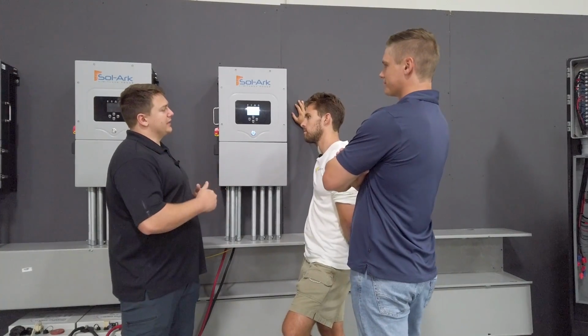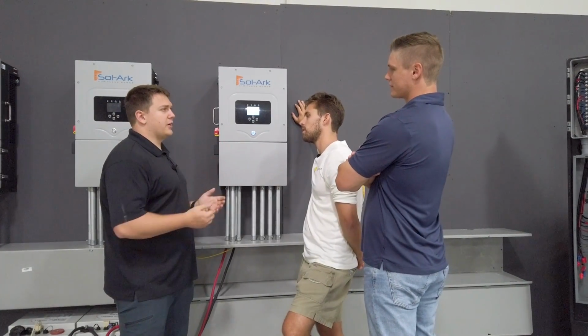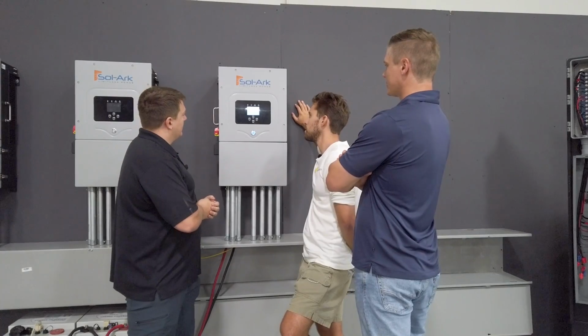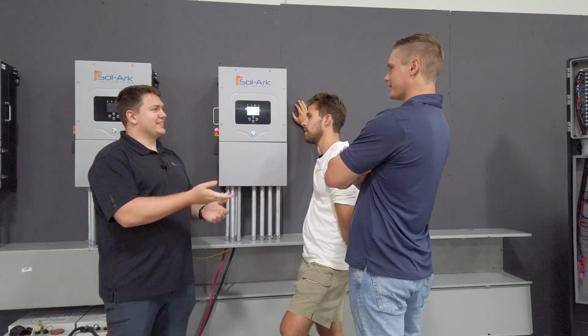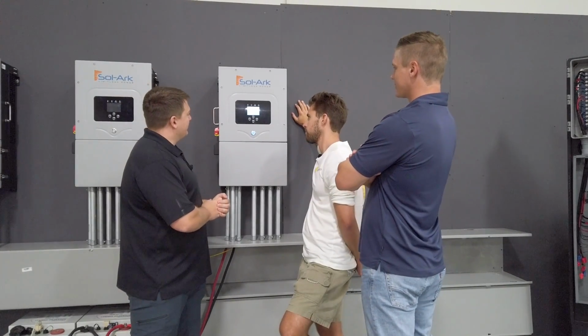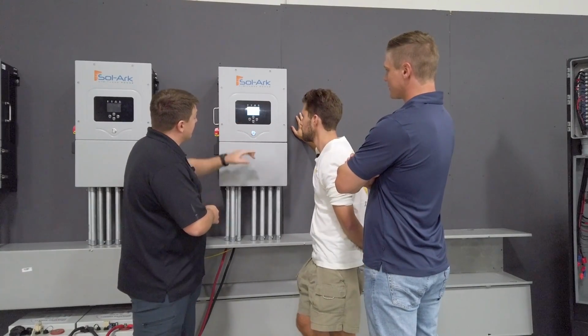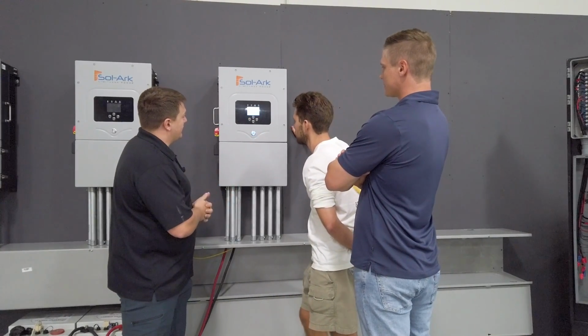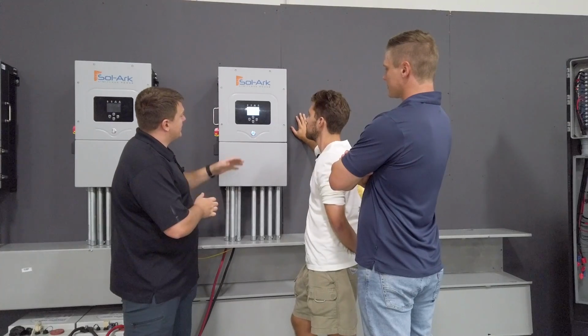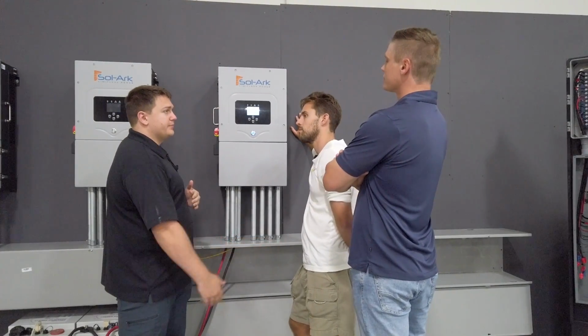Your battery's not really at that level because you're pulling 100 amps out or something. Using it at the time. Trying to start those AC units and things like that. Exactly, that kind of thing. So that's an important one to set. Again, you're going to get that spec from the manufacturer of your battery, and it does tend to go down with the more batteries you have in parallel.